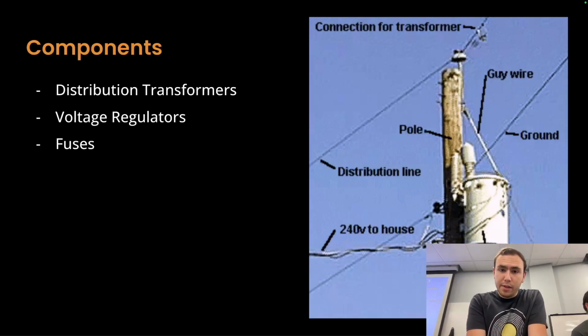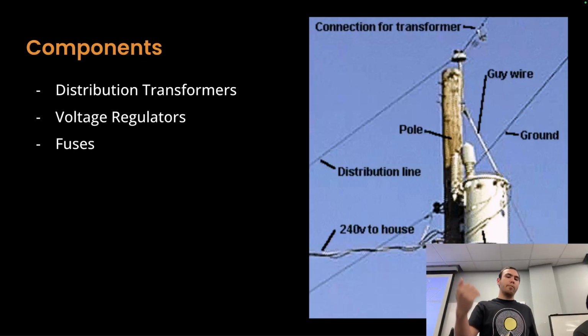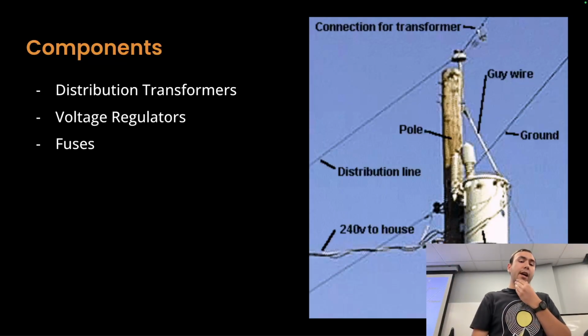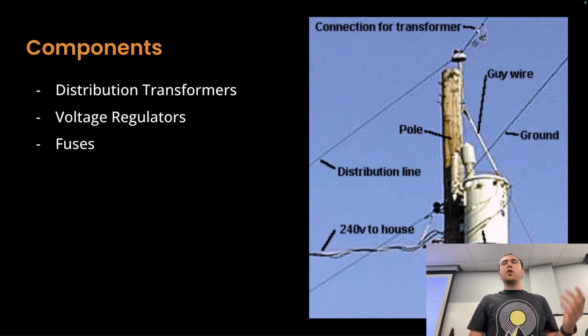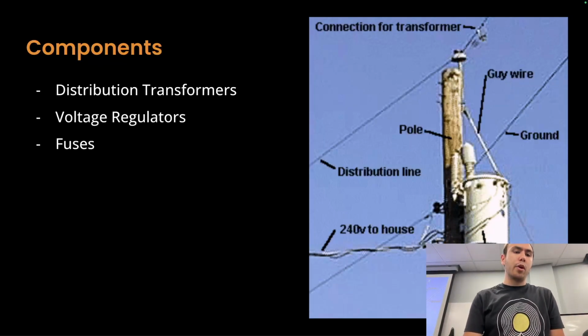We also have fuses, which aren't too important for actual security, but are really important for understanding how the grid works. Fuses are a one-time-use physical thing: you run too much electricity through them and it literally breaks the connection physically, so somebody has to go in and replace them. This is a good attack surface for attackers though, because if they take out a lot of fuses, it would require a whole lot of manual labor to go replace them everywhere they burn out.